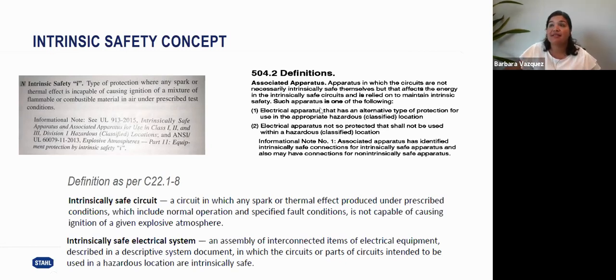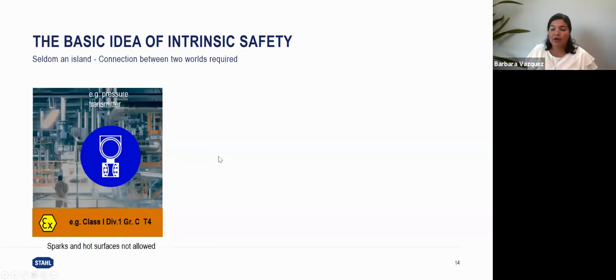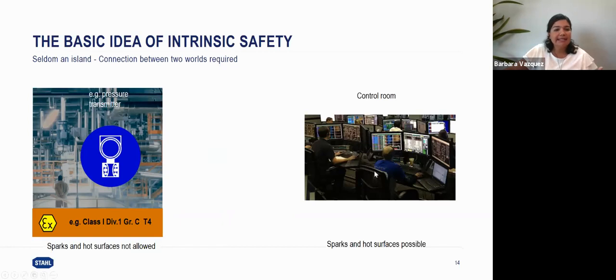This associated apparatus is a device that will be part of, or will energize, an intrinsically safe device. So usually it will have two parts, an intrinsically safe circuit and a non-intrinsically safe circuit, and it will merge these two. So I know what hazardous area I'm going to be working in. I spec out my intrinsically safe field device that is certified by a third-party agency. And in a typical installation, I have a control room where I have my PLC, my DCS, and a connection between them.